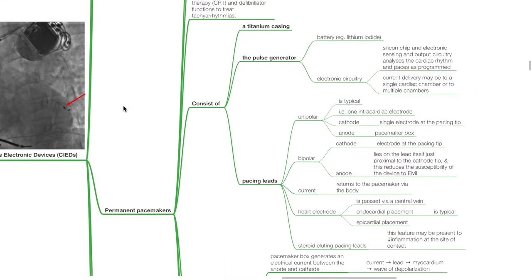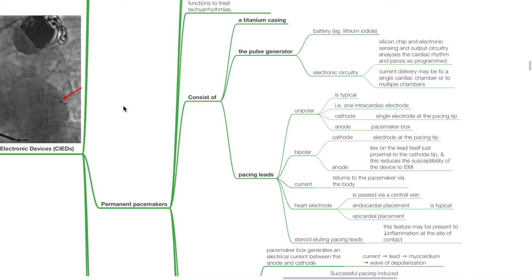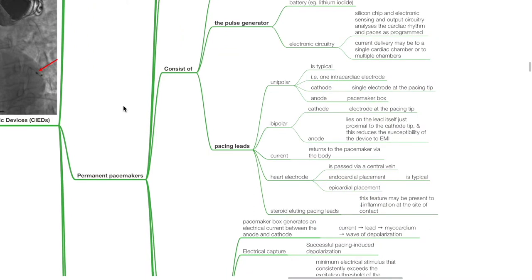Permanent cardiac pacemakers consist of a titanium casing and the pulse generator, which consists of the battery, usually lithium iodide, and electronic circuitry, which consists of a silicon chip and electronic sensing and output circuitry that analyzes the cardiac rhythm and paces as programmed. Current delivery may be to a single cardiac chamber or to multiple chambers. The pacing leads may be unipolar or bipolar. Unipolar has one intracardiac electrode with the cathode being a single electrode at the pacing tip and the anode being the pacemaker box.